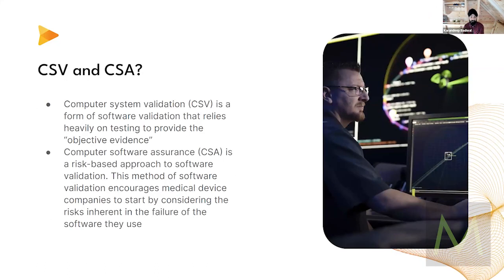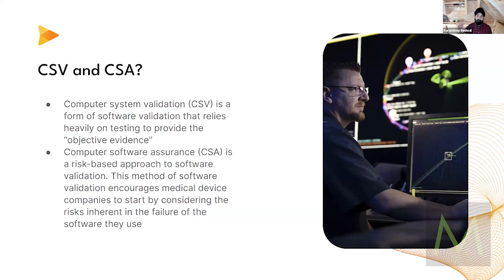The first thing we need to start off with is CSV and CSA. CSV — computer software validation — is a form of software validation that relies heavily on testing to provide objective evidence. CSV is the old system. The FDA is moving towards a more sensible system, which is computer software assurance — CSA — which takes a risk-based approach. If something is of a lower risk, you don't need to sit there doing 100 different tests. It's important that people understand the difference.